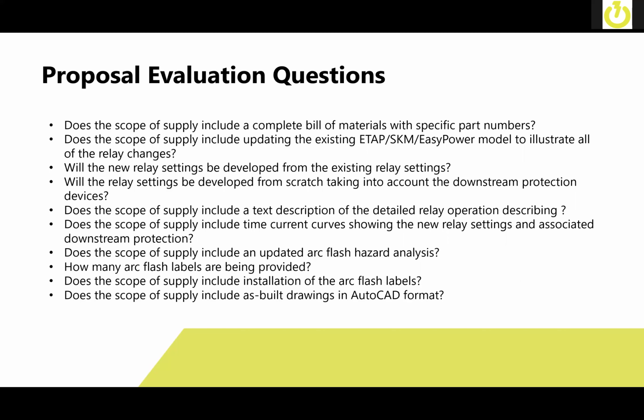Does the scope of supply include updating the existing ETAP SKM Easy Power model to illustrate all the relay changes? Will the new relay settings be developed from existing relay settings, or will they be developed from scratch? A lot of times, especially with electromechanical relays, they have very limited capabilities. You're limited to basically one type of curve that the device comes with, along with the instantaneous. And maybe you can deactivate that instantaneous or you can't.